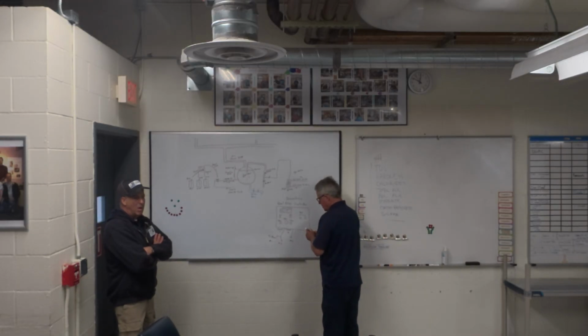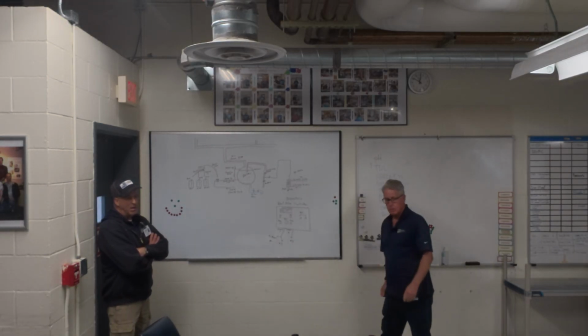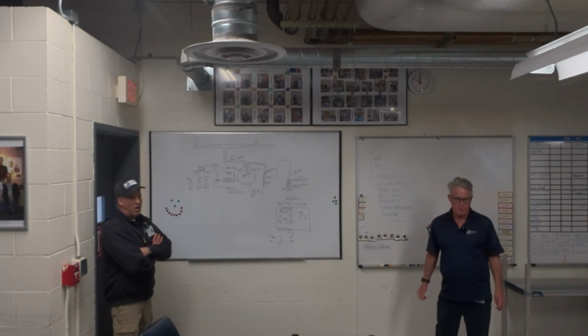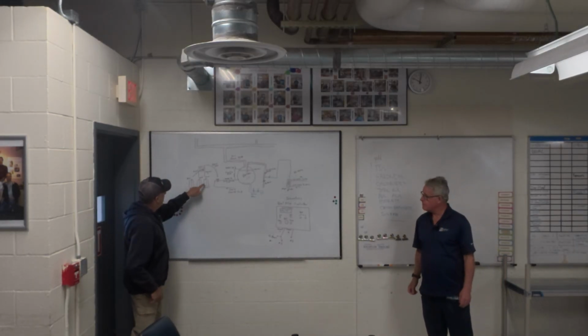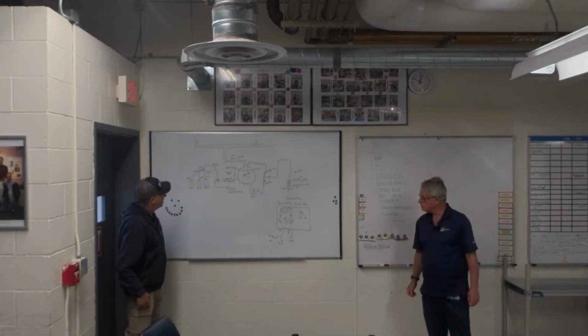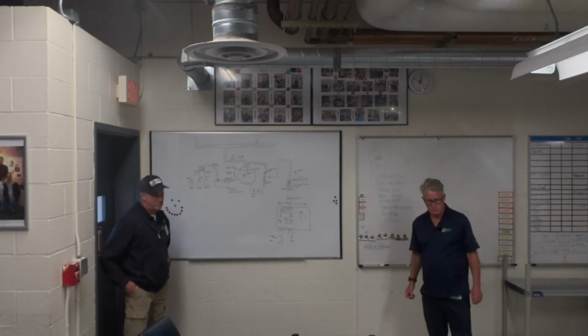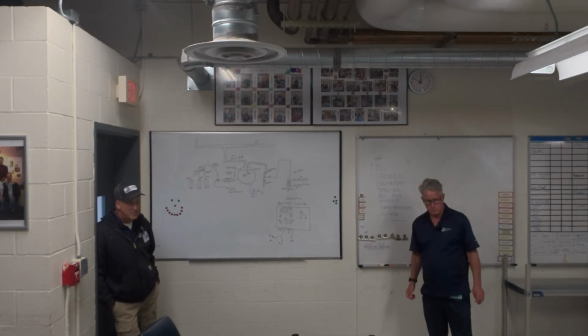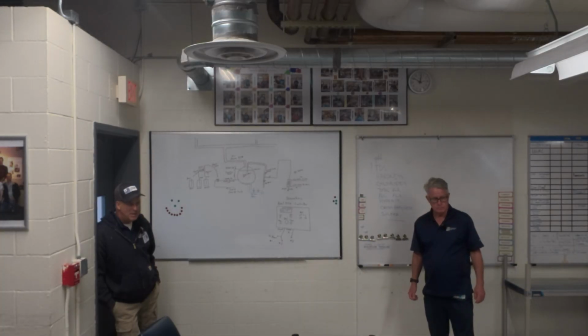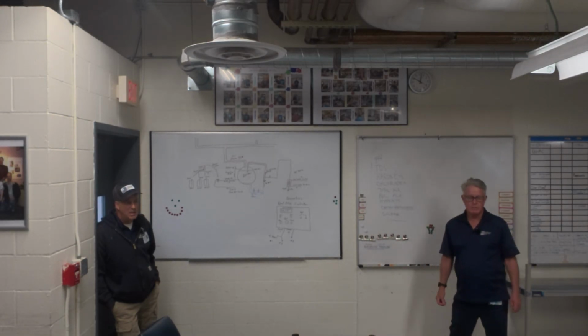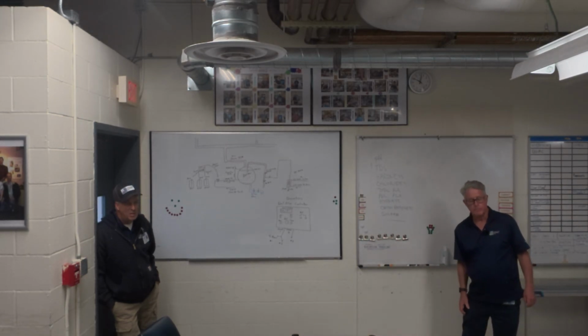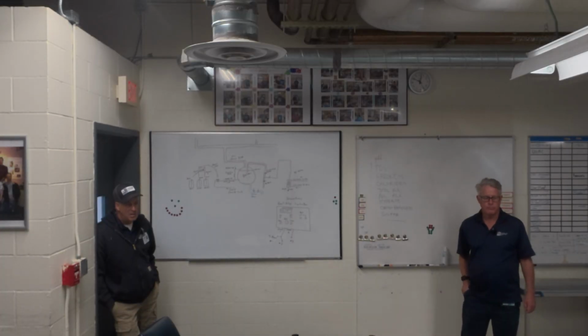If the flow line gets plugged up, the Symmetrics really doesn't monitor what's happening at the pump. All it's doing is taking the count of the flow meter. The flow meter pulses for how much flow goes across it. The Symmetrics counts those pulses and tells the pump to run. That's all it does. It doesn't know what the pump's doing, and it really doesn't know what the flow meter's doing. It just knows that the flow meter says that it flowed.